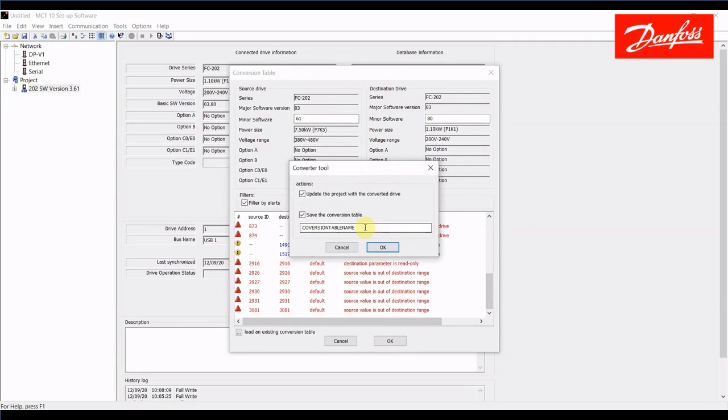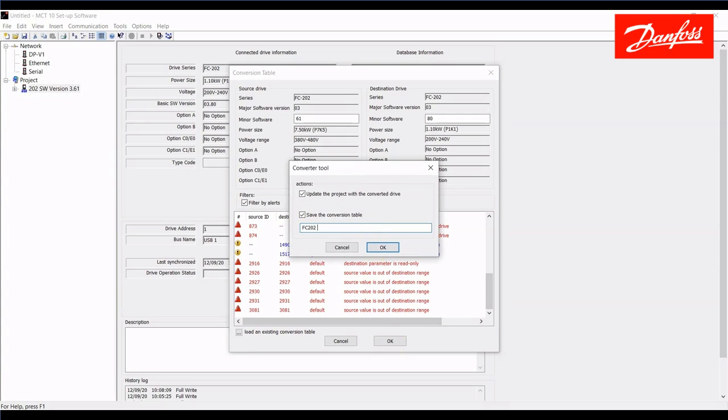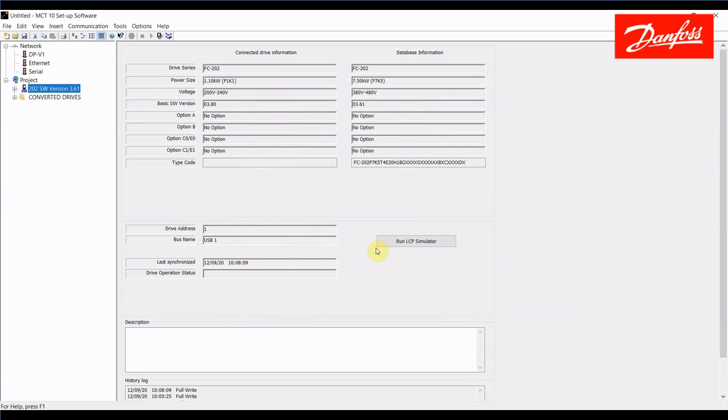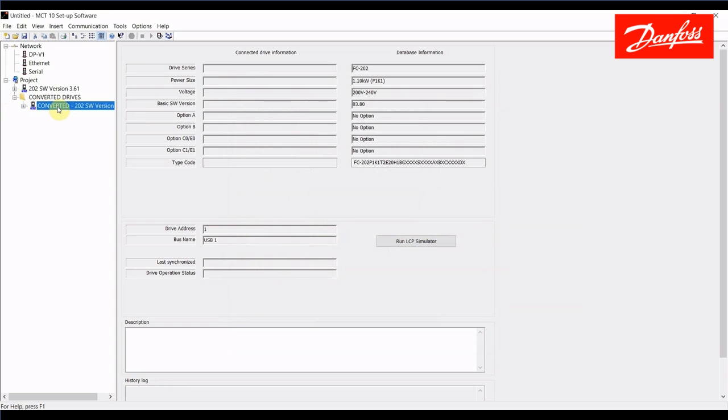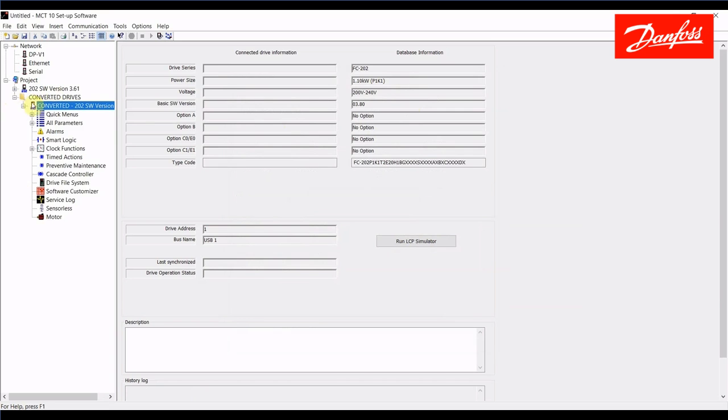It's going to ask you to name this conversion table. It will actually save it in MCT10 so if you were to go to write from 3.61 to 3.80 again you wouldn't need to go through this it would just be a clean write. So I'll name that file and save it and at this time it updated my project. So here we have the converted drive and now we're looking at a 202 drive that's been converted to software version 3.80. If there were any parameters in this project that didn't exist in the older one I can address them now and save the project and now it's converted.